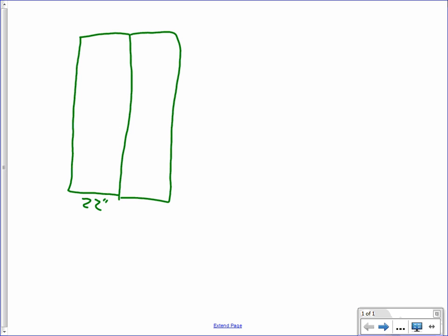Same with anything below that. When we get to the 4,000 or 5,000 amp breaker, then we're into a 36 wide section. And normally a 3,000 amp is what we call a double size breaker. In other words, it takes up two cubicles in the gear. So this would be our 3,000 amp main.